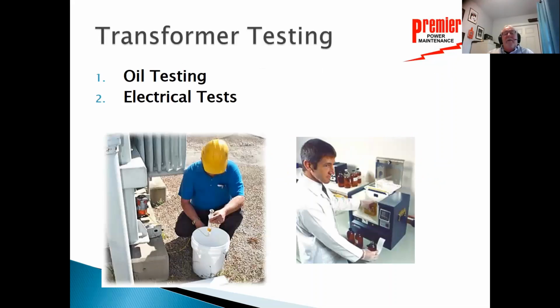One of the easiest and simplest things that we can possibly do for a transformer is to test the oil. There are 2 different types of oil tests that we perform. One oil test is called an oil quality screen, which is for testing how well the oil is. And we can do dissolved gas analysis, and then we can also do electrical tests as well. We're going to spend a little bit of time talking about the oil test that we want to do on this transformer.